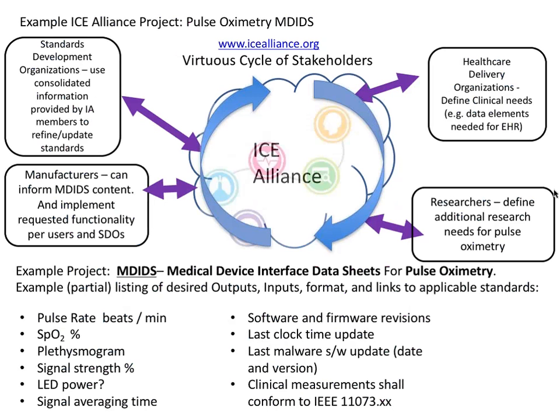We've had a project for several years called MDIDS — Medical Device Interface Data Sheets — think of it like material safety data sheets, where we can start as a community to identify all the desired inputs and outputs for medical devices. Standards development organizations can have a consolidated set of information to ensure standards are aligned. Manufacturers can provide input in terms of what they need to implement. They have time to modify devices to meet the needs of healthcare delivery organizations and researchers. This project called MDIDS is the kind of thing we're providing into the ICE Alliance.